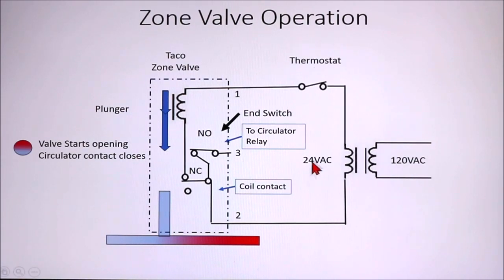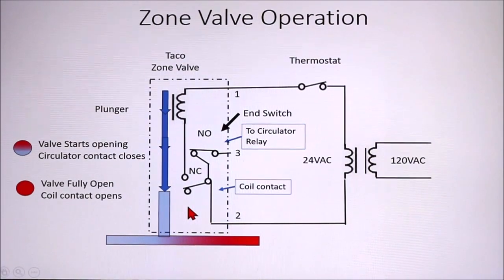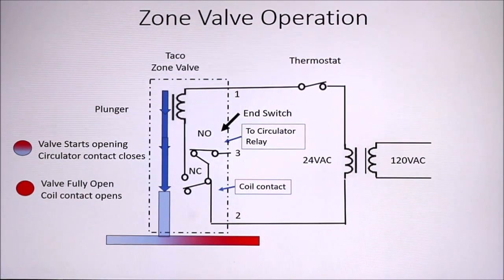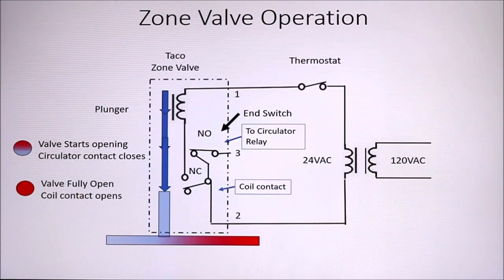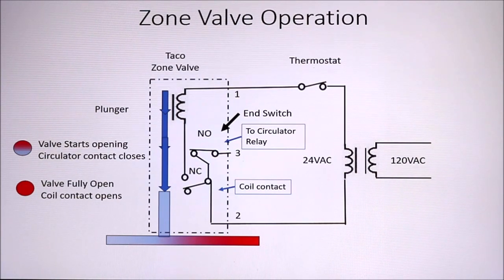As it continues to heat up, the zone valve pushes the valve fully open. At the same time, this normally closed contact, which has been powering the zone valve, opens up. And without that, the zone valve would get very hot and would also keep pushing on the zone valve and keep it open.